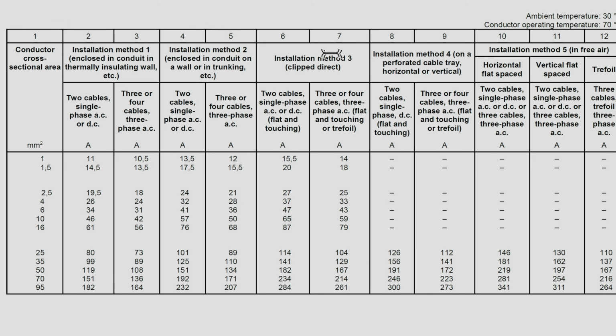Okay, so I'm going to look here on this column which says installation method clip direct. Now, it's not going to be clip direct. It's probably going to be more like in free air, but there isn't a rating for this size conductor. So I'm just going to look at this one for now, and I can see that if I use a 10 millimeter cable, whether it is AC or DC, and the two cables are running together, which they will be, I can see that the current rating, the nominal current rating, which means that it should be able to provide this continuously, is 65 amps. So I can already see that that's quite close to the maximum current, but in my case, I would say rather go one size up. So if you go 16 millimeter, you'll have a lower volt drop, which is very important for DC applications.